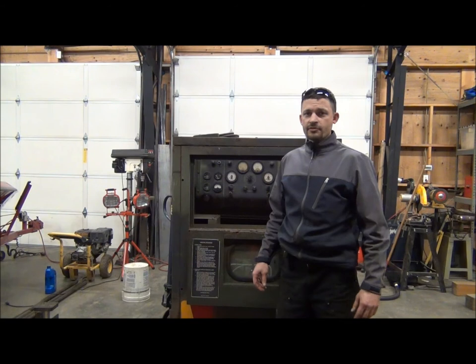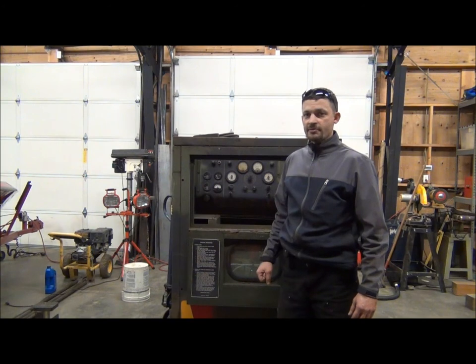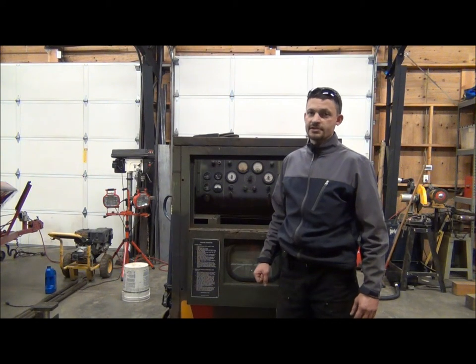What I'm going to do tonight is take you through the procedure for converting one of these three-phase military generators over to single phase. This unit behind me is an MEP004A — a 15 kilowatt three-phase diesel generator that comes pre-configured in either 120-208 three-phase or 240-416 three-phase.